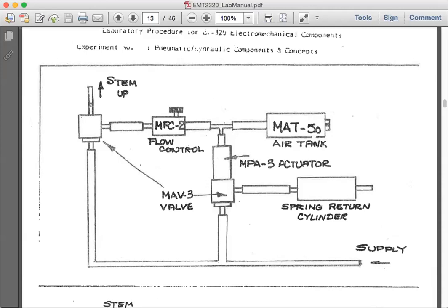And this stage 3 would indicate that when you release the stem, you don't immediately depressurize the whole system because you have the flow control. If you release the stem and you didn't have the flow control, then basically you would say, okay, this is all blue, it's venting, you had the depressurized actuator, and everything is returning back to the initial.